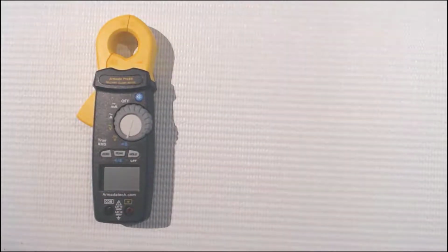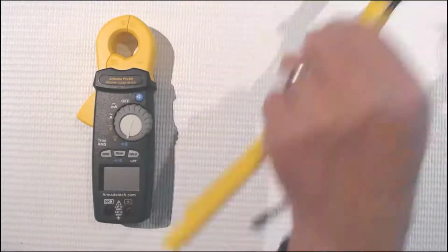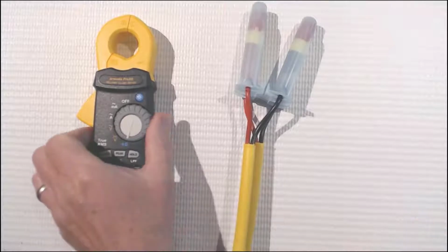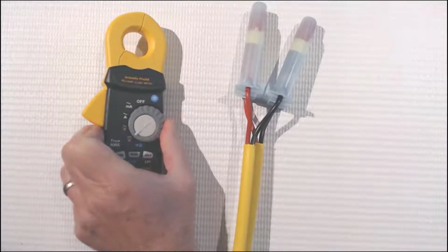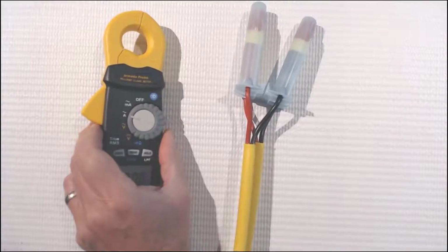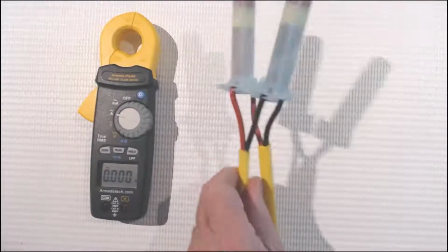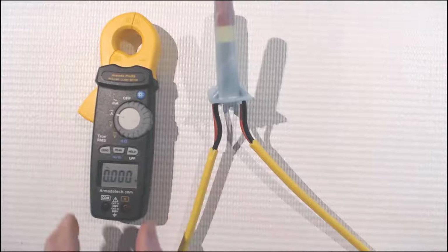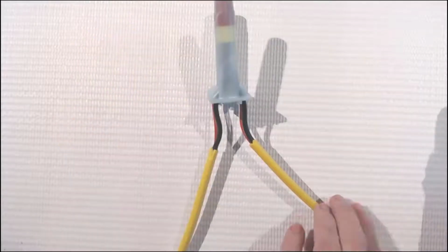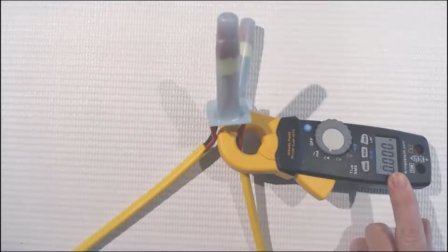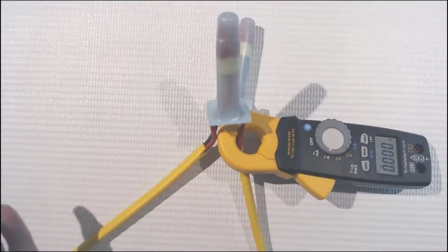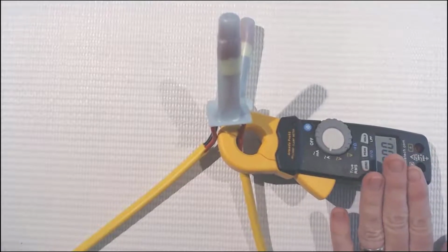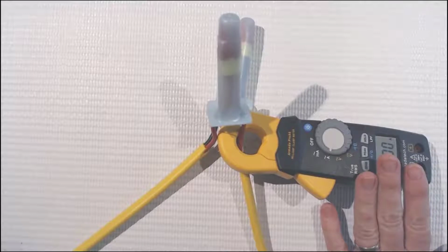So let's first talk about where you might use the milliamp clamp. You're going to use a milliamp clamp primarily on 2-wire systems. In that case, you're going to set the meter to AC amps, which is the A with the wave sign on it. And we are primarily going to use this as a non-invasive way to check for an overcurrent. So we'd come out to the field and clamp that around one side of the 2-wire path, and then get a reading. This would tell us the amperage draw downstream of this point, so this will help us pinpoint an overcurrent. If you want to know about overcurrent troubleshooting, you will find that in another video, which I'll put in the show notes. So that's primarily what this is used for.